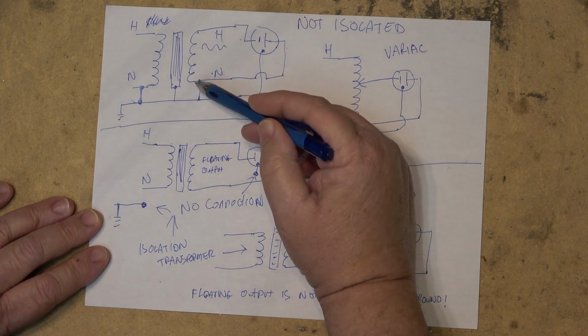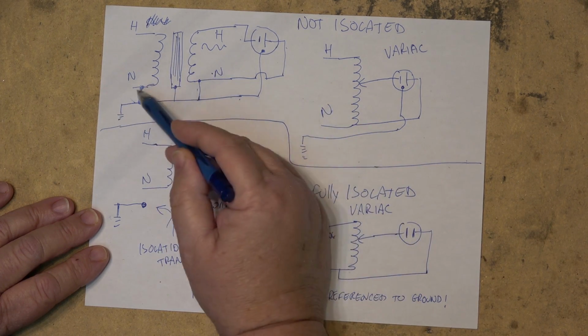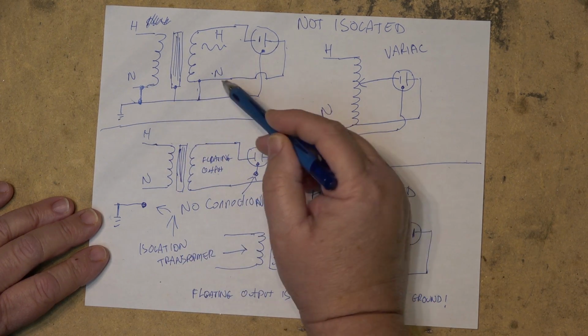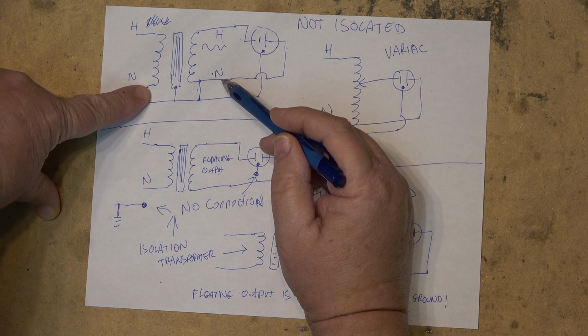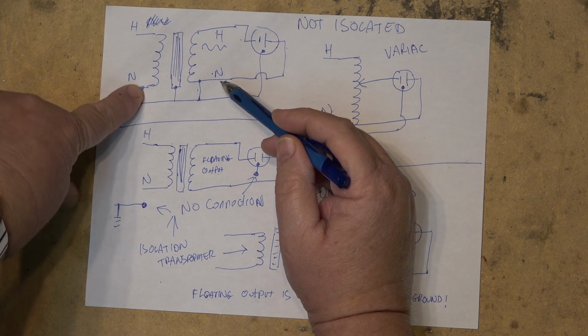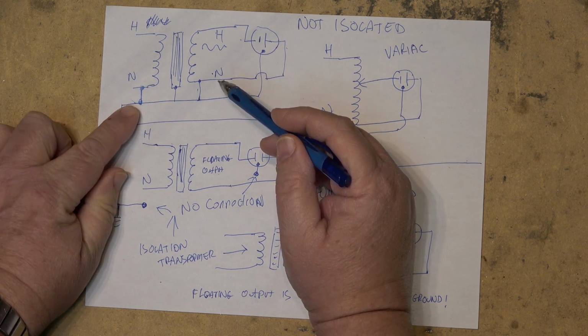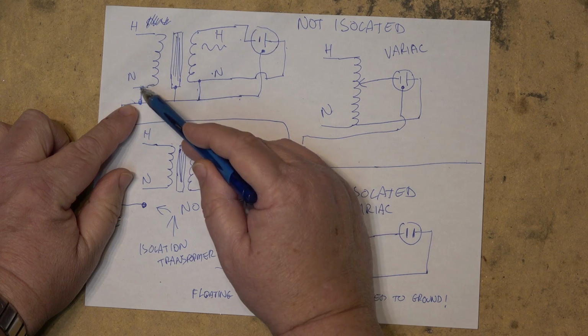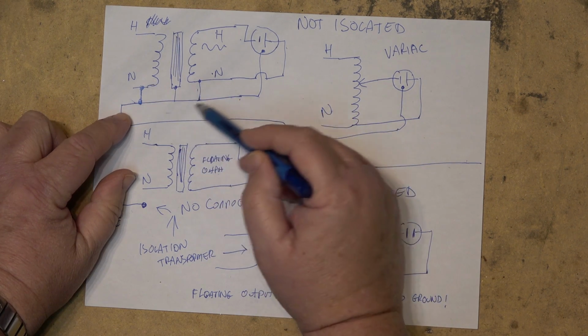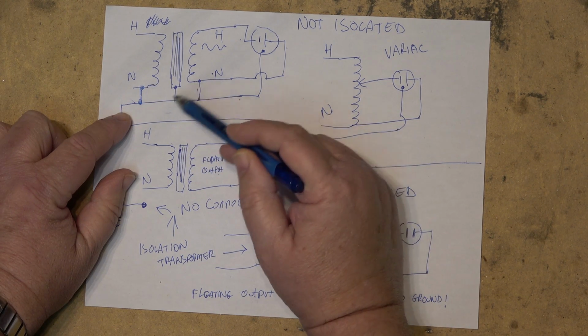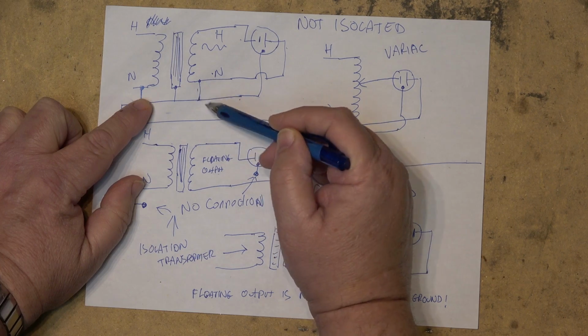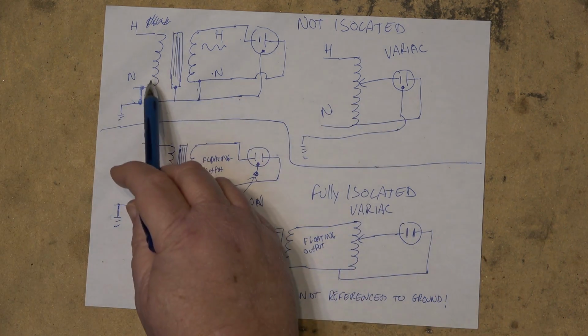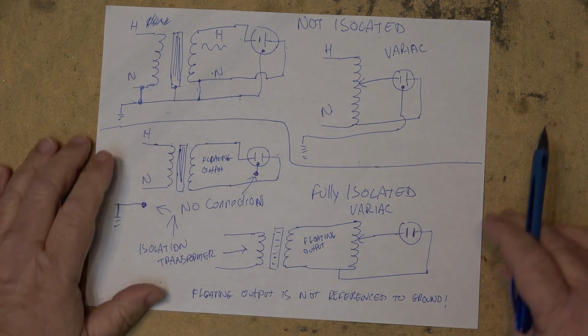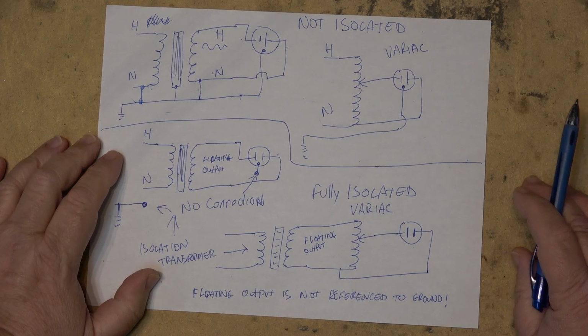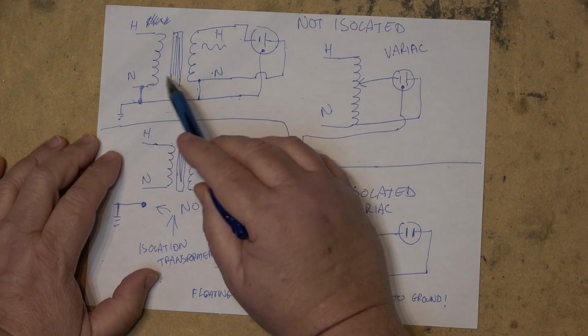Because one side is referenced to ground, which is connected to the neutral. So in this case, I drew that in just as a reference for how your house wiring is. Most of these transformers, some may have the neutral bonded to the ground as well. Others may only have the secondary bonded. But here's the problem. I mean, the primary side can be bonded. That's not going to affect anything. For that matter, the transformer case can be bonded as well.